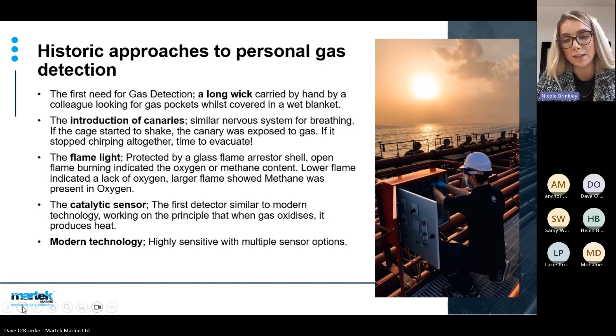In addition to the ever-evolving way of detecting the gases themselves, there's also been quite a shift over the past few decades in how gas detectors were calibrated. So traditionally, gas detectors were placed on board vessels. They were calibrated by shore-based service providers, meaning that the detectors were sent back to land. A service company would do the needful. They would check they were working via calibration and bump testing, and do any necessary maintenance that may include battery changes and sensor swap outs. As you can imagine, this can be quite a costly process.